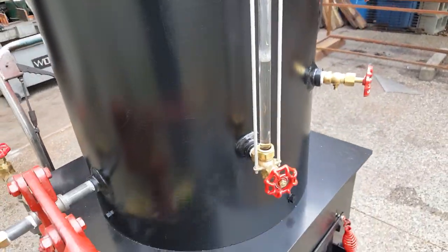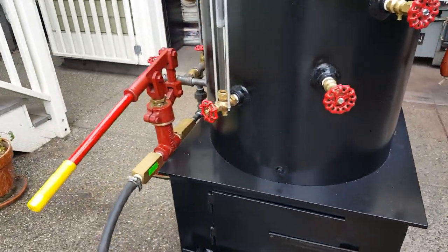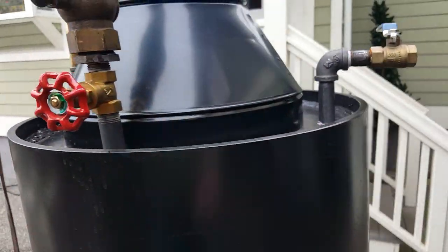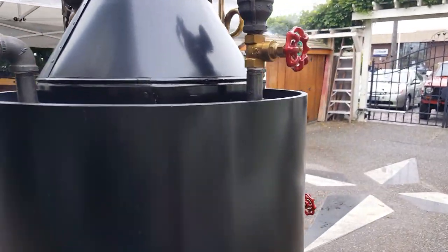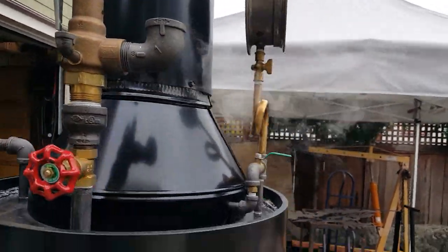Water sight glass is in good shape, no leak. High cock — perfect. And like I say, I'll remove all of this later. This is your engine out, half inch pipe. I'll remove this valve too, now that I know that the pop off valve works properly.